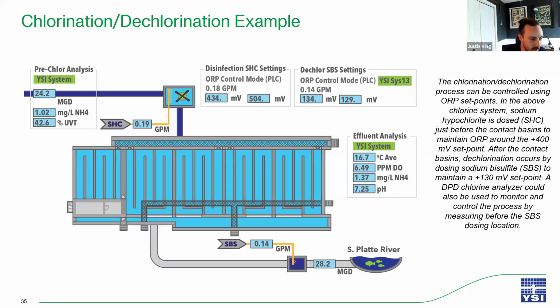And then at the very end of the process, you would want to have a chlorine analyzer to ensure that the sodium bisulfite has dechlorinated down to the permit limit. This can also be done with ORP measurements if a chlorine analyzer is not applicable or is not in the budget, per se. ORP values, the millivolt values, can correlate to the amount of chlorine in a system, but all the processes are very similar.